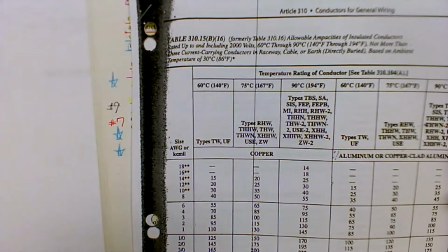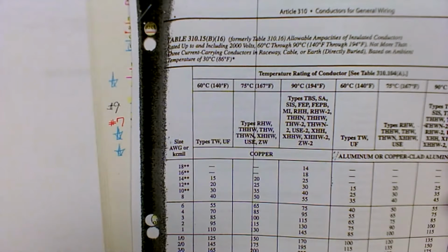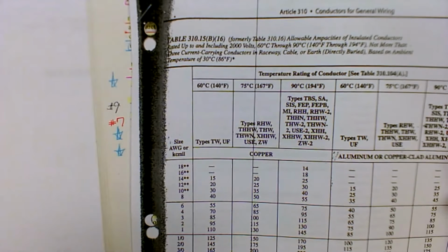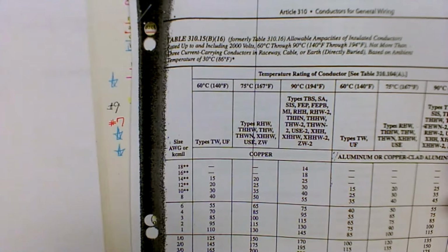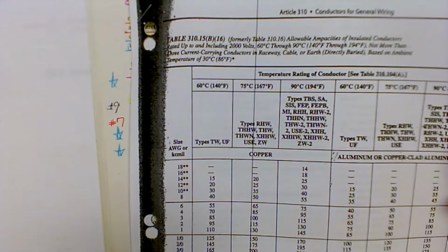Sometimes you go receptacle to receptacle, and they got a bigger breaker, bigger wire, and sometimes they run individual runs to each one. Typically, 1 fan is always wired up by itself as an emergency. So that'd be 4 fans. Would that be 2 conductors per? So 8 current carriers, and each one would have a ground. You don't count the grounds in this.